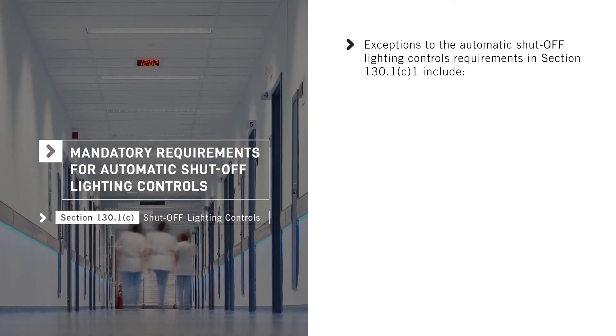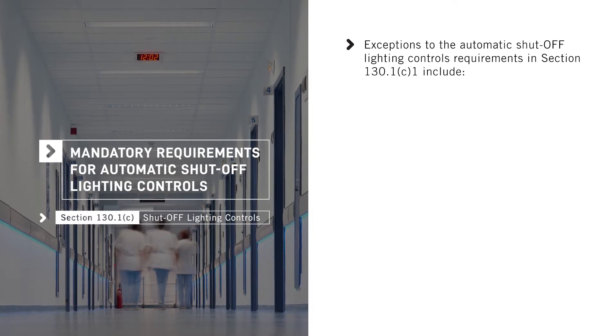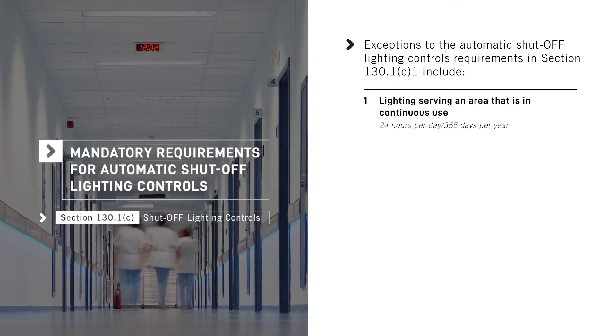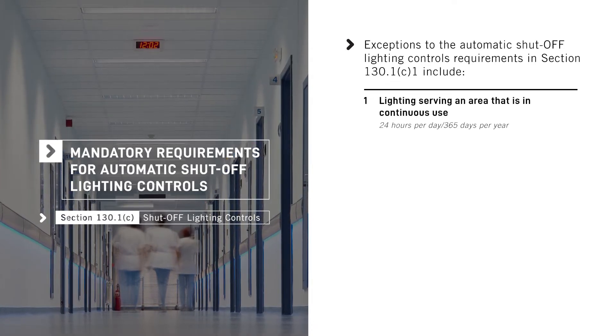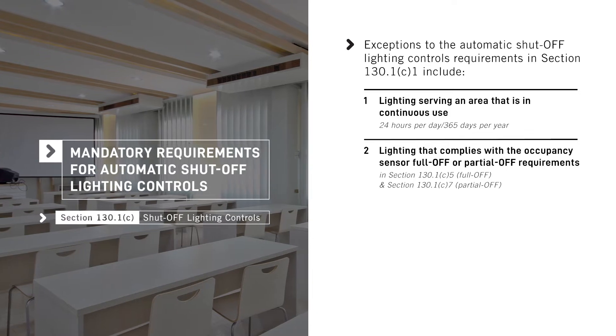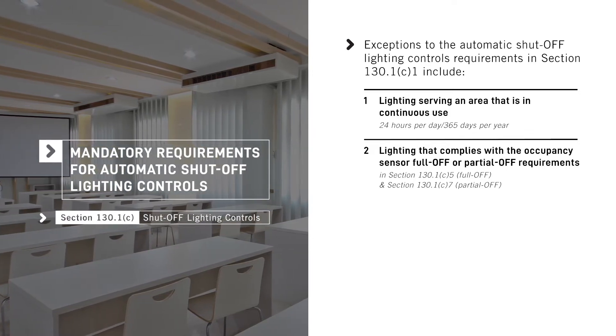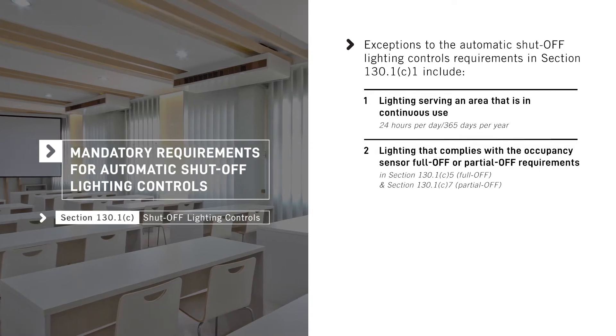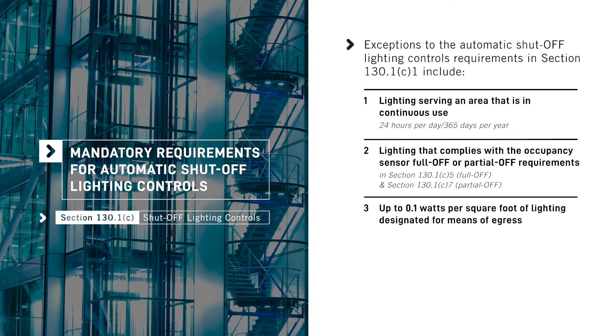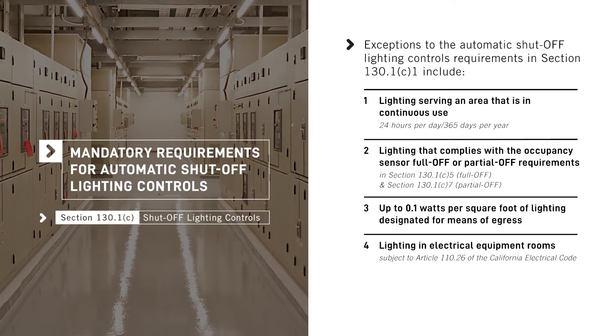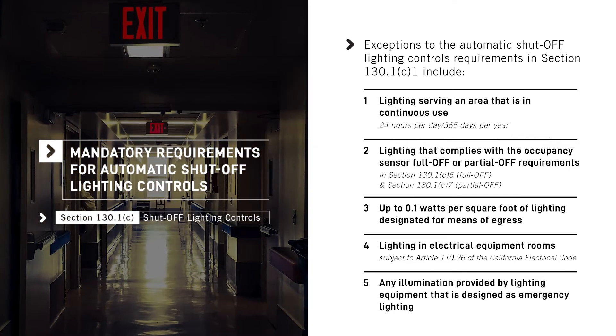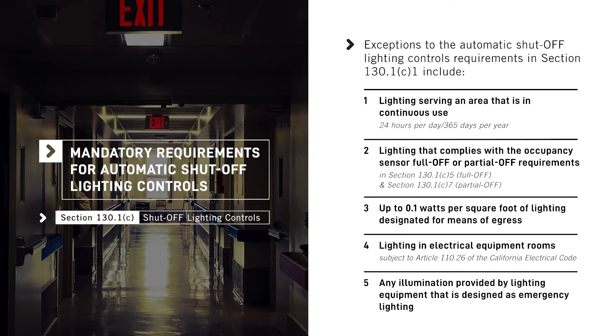There are a few exceptions to the automatic shutoff lighting controls requirements in Section 130.1c1. These include lighting serving an area in continuous use 24 hours per day, 365 days per year; lighting that complies with the occupancy sensor full-off requirements in 130.1c5 or partial-off requirements in 130.1c7; up to 0.1 watts per square foot of lighting designated for means of egress; lighting in electrical equipment rooms subject to Article 110.26 of the California Electrical Code; and any illumination provided by lighting equipment designed as emergency lighting.